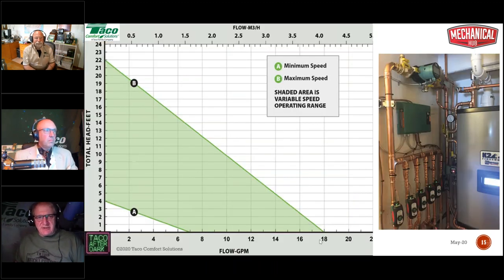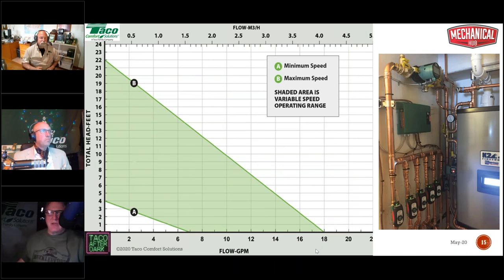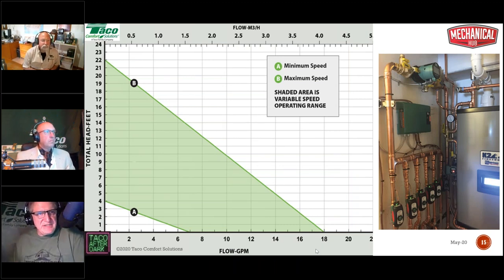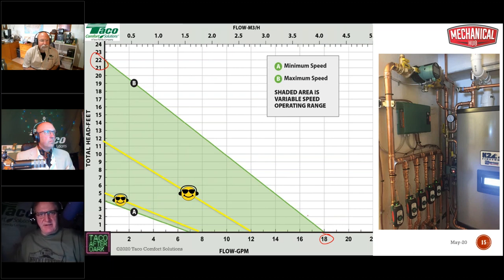What you're looking at here is the pump performance curve of our delta T circulator, the VT2218. The VT2218 gets its name from 22 feet of head all the way down to 18 gallons a minute. This green wedge is very important because that's the operating parameters of the VT2218. It can't go any faster than line B, and this is important, it can't go any slower than line A. It has a minimum speed. It just doesn't go down to nothing because the math says it can. I mean, that would be silly.